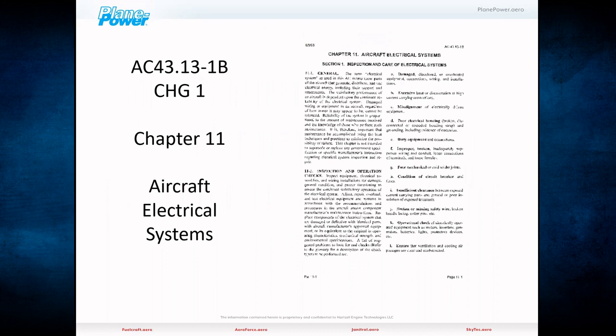AC 43.13 has been around forever. When I was in A&P school, this was the Bible. The manuals weren't as good as they are now, so this was the best reference information out there. It's acceptable data, not approved data, but it gives you wire sizes, cable sizes, circuit breakers, fuses—everything you need to build an electrical system in the airplane. I send all the home-built guys to this, because I'm not the reference; they need to be able to say, I did this in accordance with 43.13.